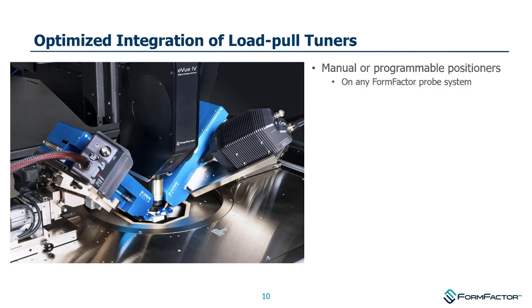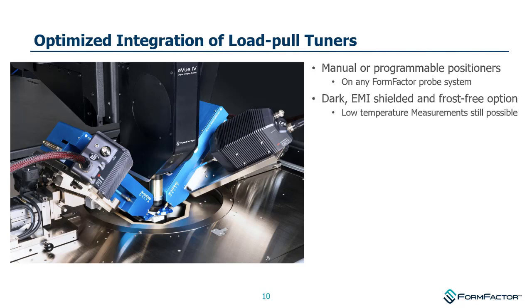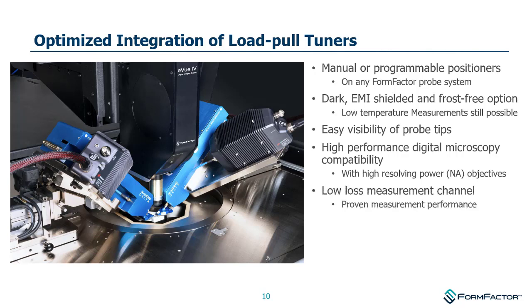The positioners we can use with these include motorized or manual options, and they can be used on any of the FormFactor station platforms with the same base positioning arrangement. We can perform some limited thermal work even in an open environment, or we can modify the setup to go to a closed environment comparatively easily. We have good visibility of the probe tips and can use high-performance digital microscopes. This is something we have really tested — it works and is at customer sites right now.